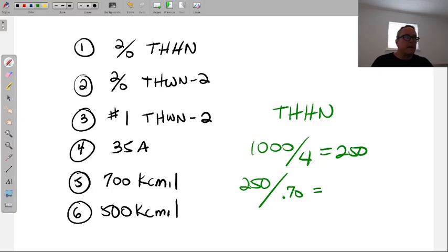So there's an easy way to parallel. To parallel 4 wires, divide the amperage by 4, go find that wire. But now we're putting 8 of them in a conduit. Again, this reduces the amount of conduits I have to use. But that's going to make the wire a little bit bigger because I have the temperature to deal with when I have too many wires in a conduit.